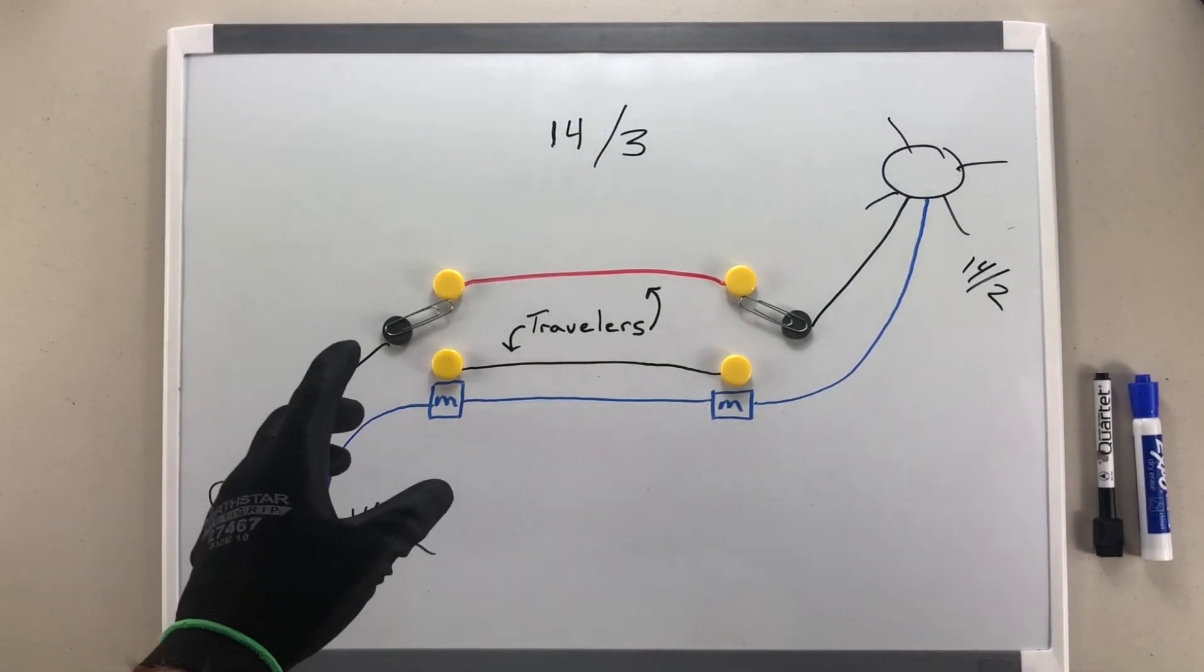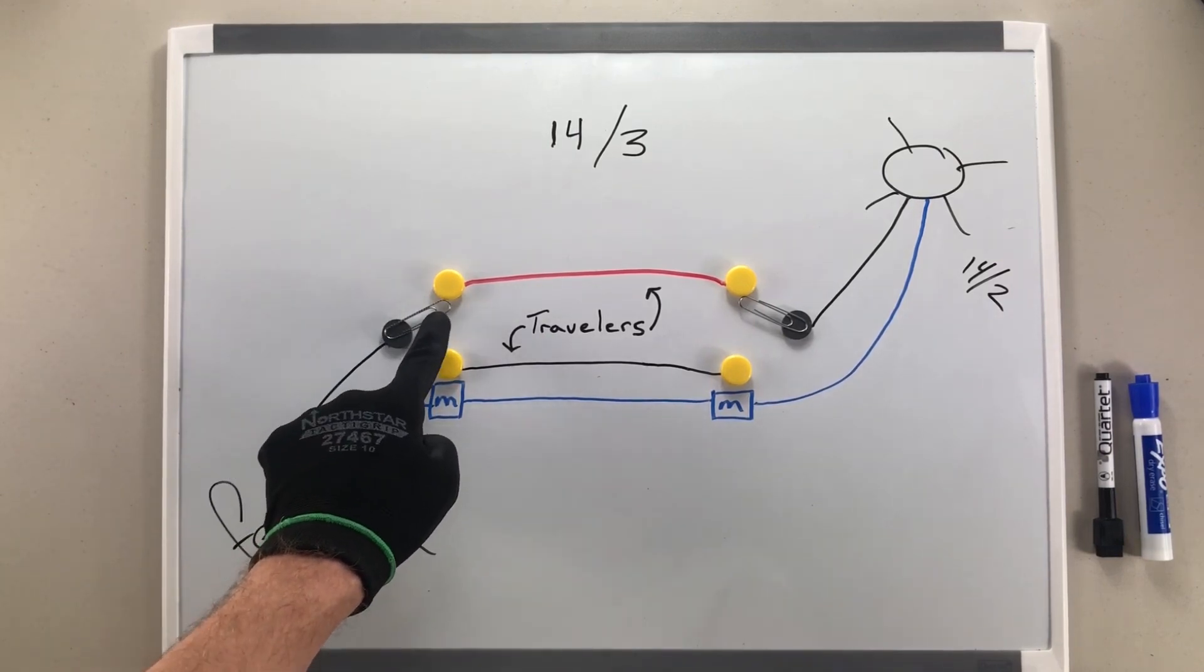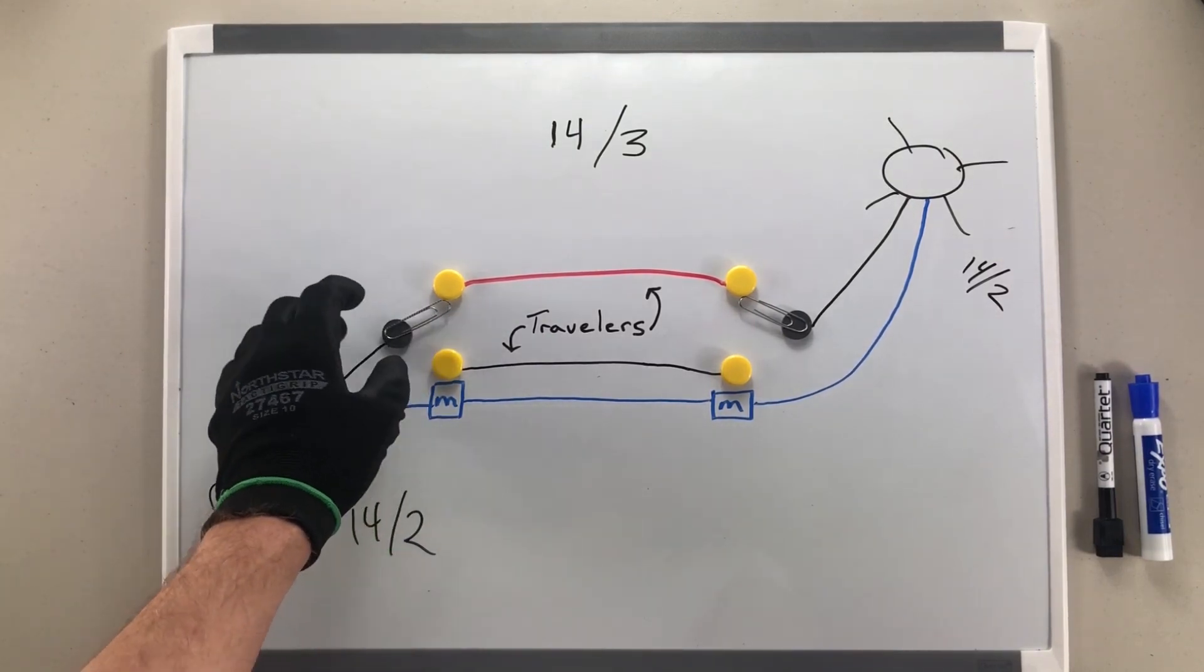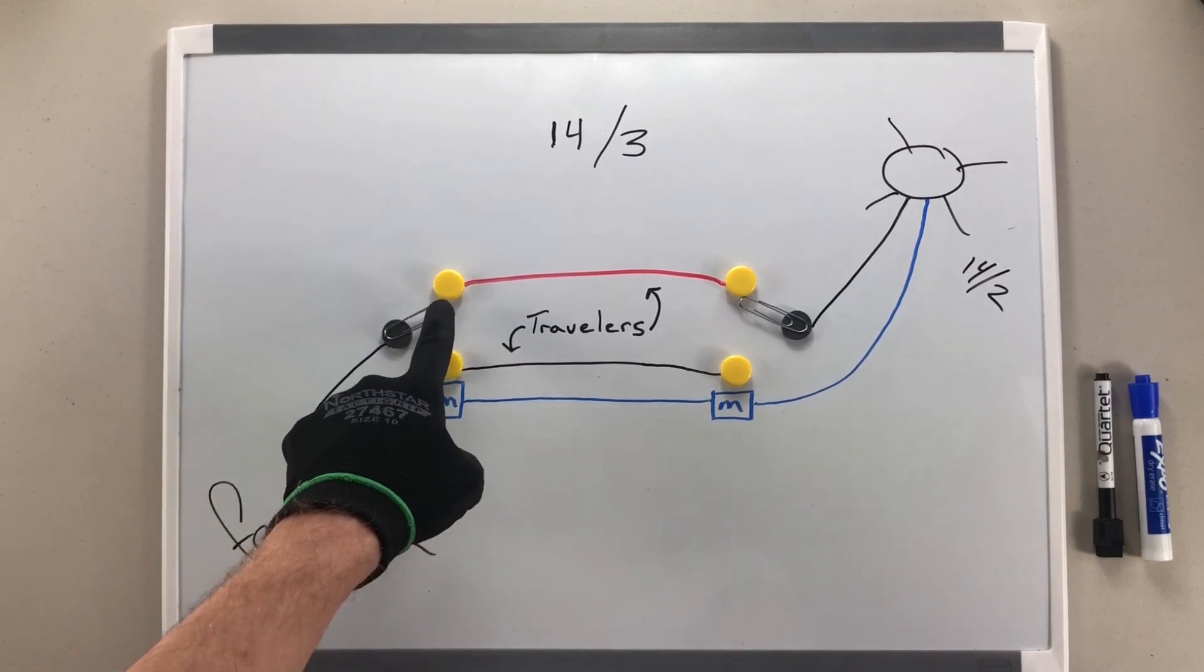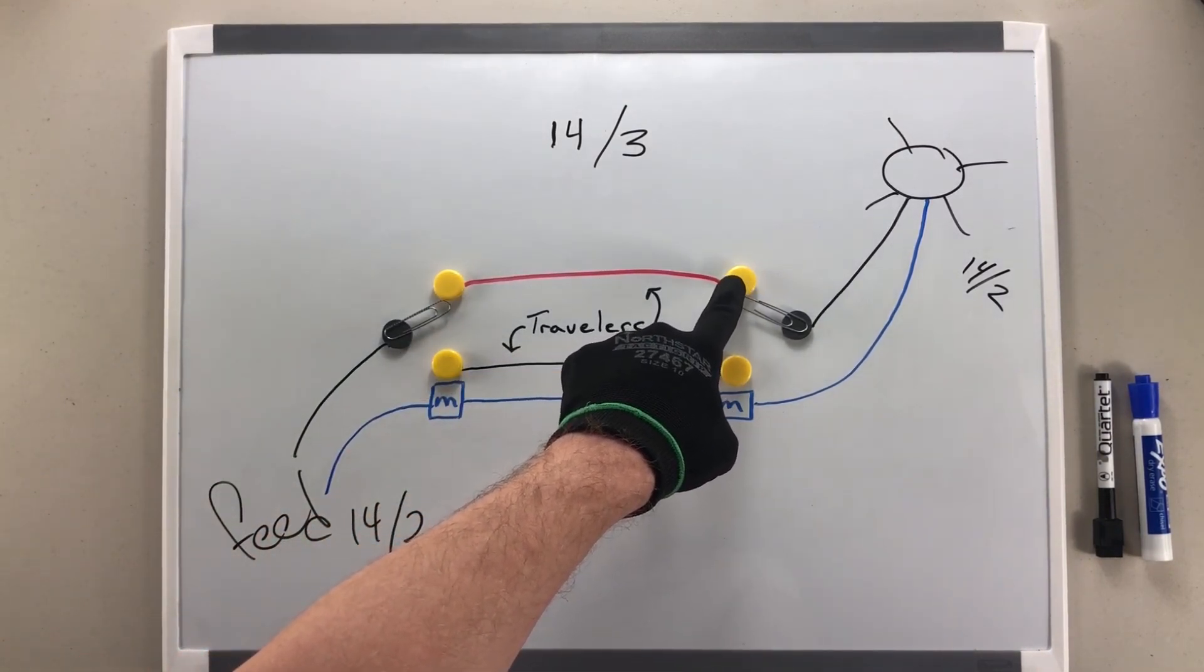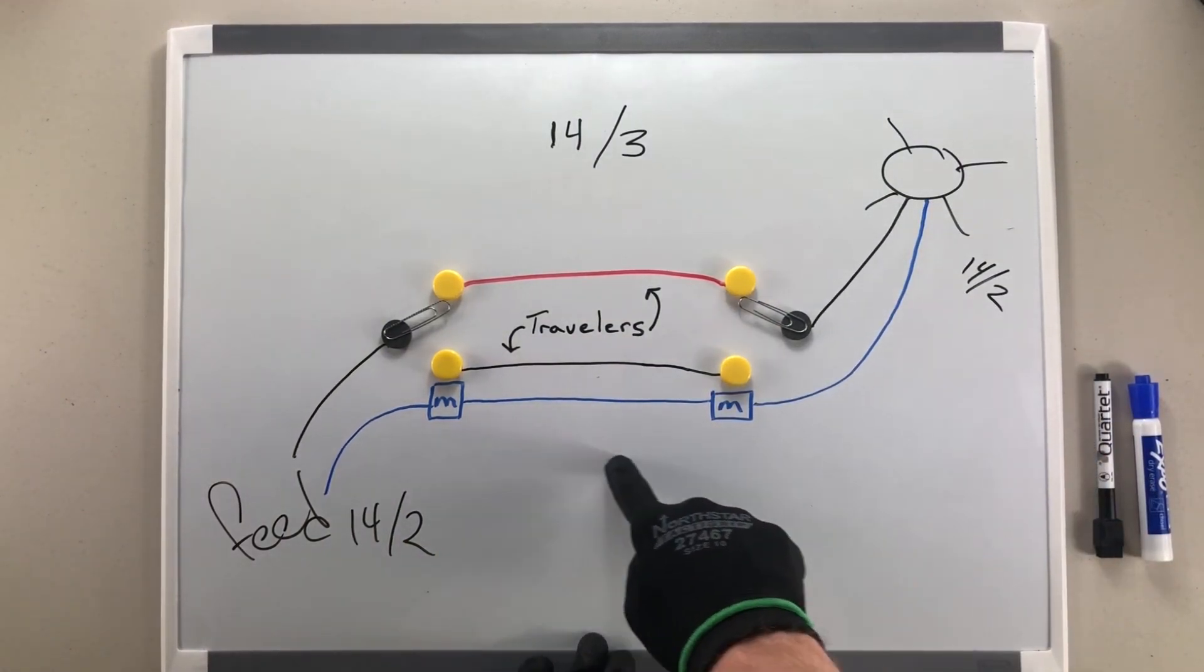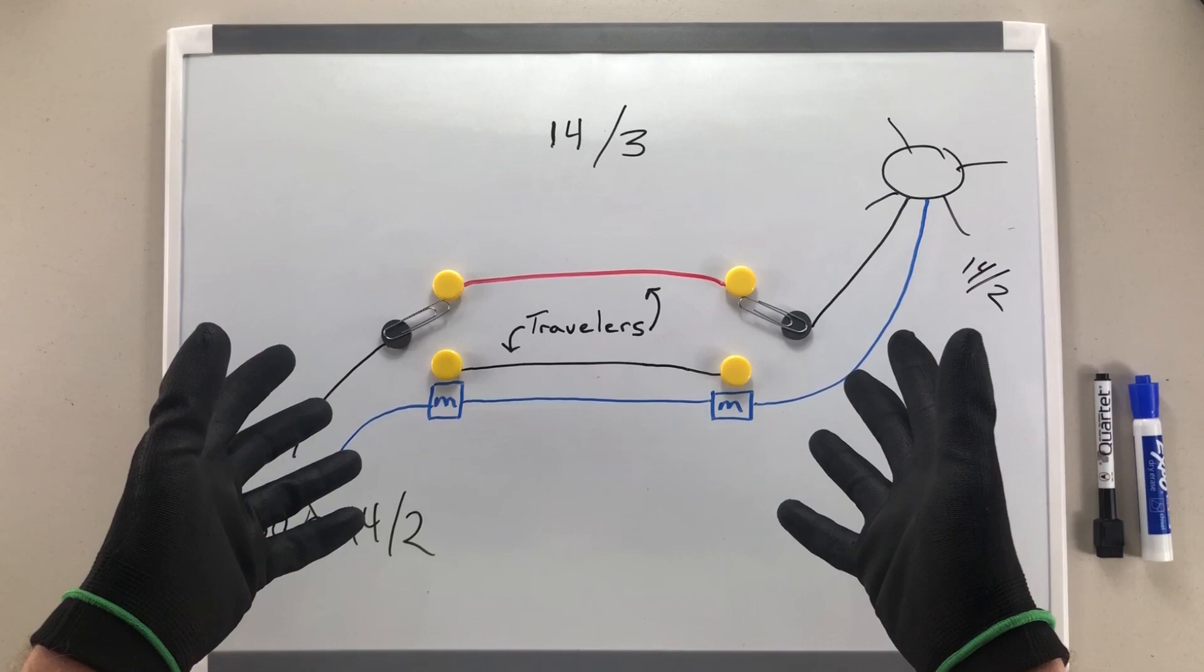The way this works is your power comes in on your common screw here, up through your knife blade inside your switch, and into your traveler terminal here, across to this traveler terminal, down into your common screw, up into your light, and returns on your neutral. In this condition, the light is on.